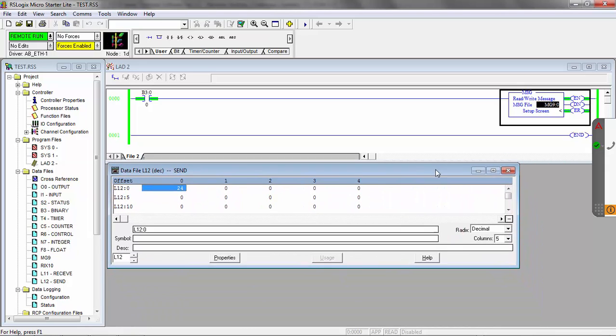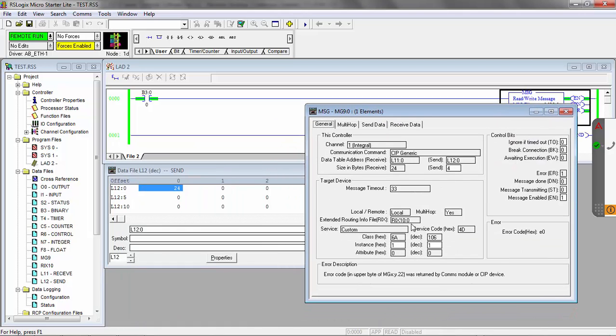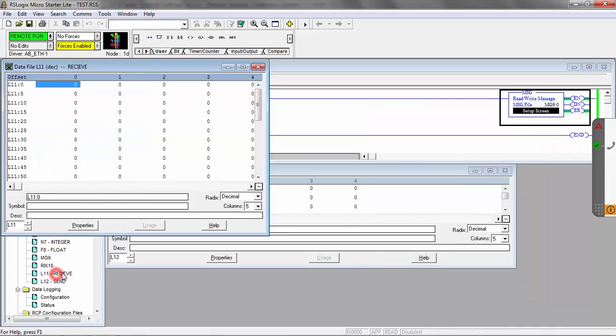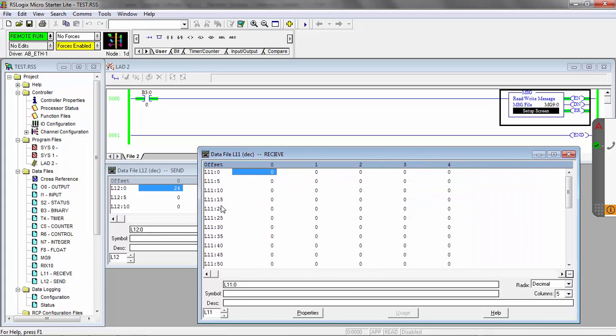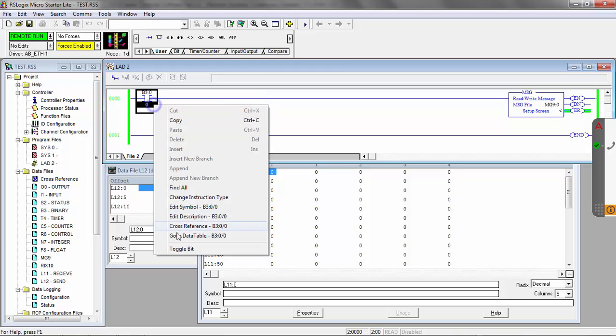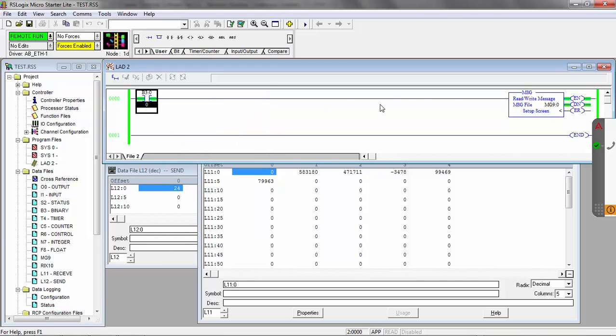We have our send information all set up. We're going to receive our data into L11. Let me open that up — when I issue my command, we should receive six data items. Let's go ahead and manually toggle this bit for the message. Once the message is sent, if it's successful, the done bit will turn on. If there's an error, the error bit will turn on with an error message. It looks like we got our done message and the data has populated. The total status was the first data item — even though it's a pass/fail bit, it still occupies one location in the output. It's showing zero.